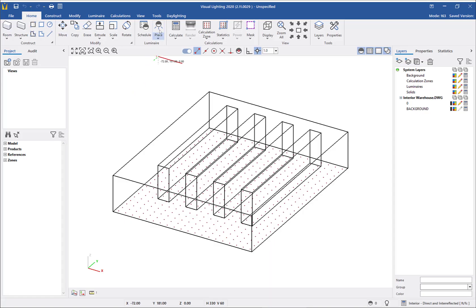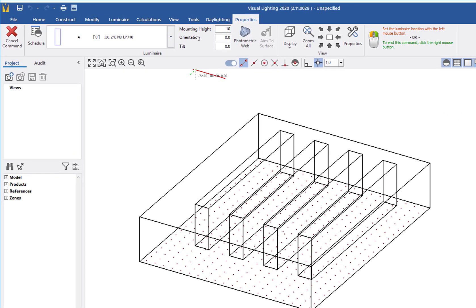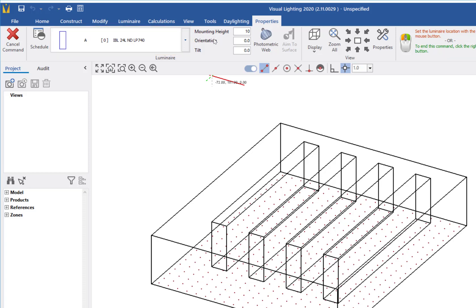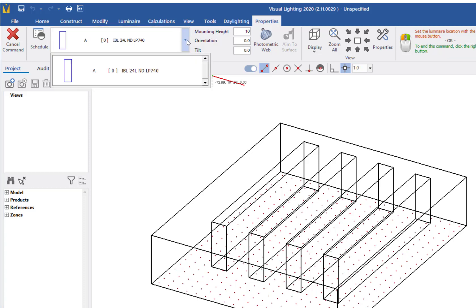In the design environment, to place a luminaire in the design, select the place button. The ribbon will change to display properties related to the luminaire. There is a dropdown list of luminaires that I can place. Since this is the only luminaire in our schedule, that is the default option for placement. First, I will set the mounting height to 24 feet.